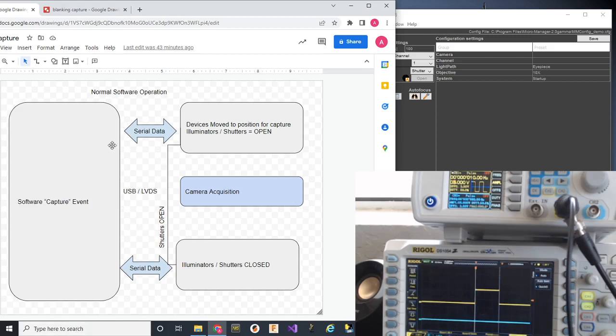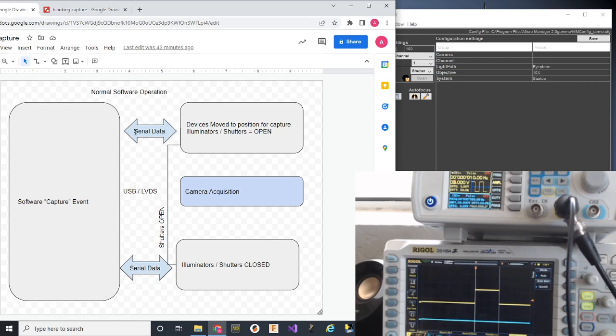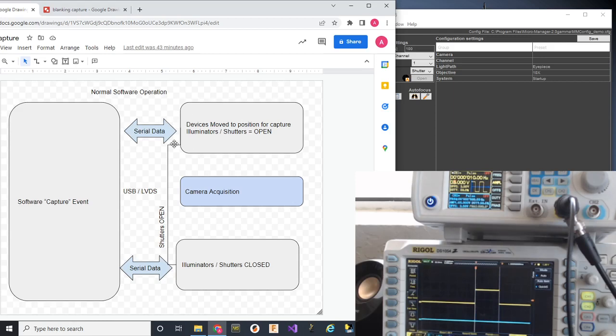this is the software capture event. What goes on in the hardware? The first thing that happens is all of the devices connected to Micromanager, maybe that's a dichroic wheel or a filter turret that has cubes in it, maybe an emission filter, and then different illuminator types like lasers, LEDs. They're all set up typically via USB to serial or direct USB.